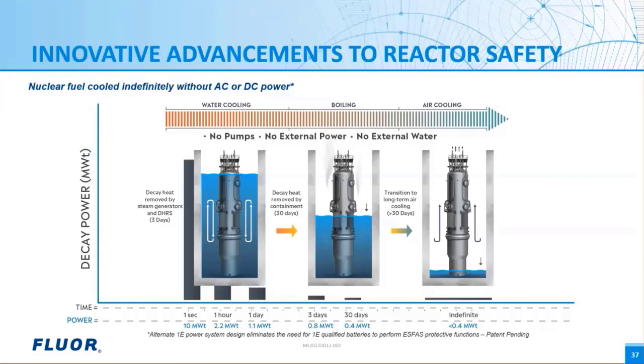Evacuating that volume also removes oxygen from the containment and thus it minimizes the possibility of a hydrogen deflagration. Finally, when the water level is below the level of the fuel, you're now cooling via air cooling. And that is sufficient air cooling to remove the decay heat, which is now down to a low level after 30 days. Note that while the reactor is known as walkaway safe, that's not the normal practice. Operator intervention and restorations of systems is the norm for cooling. So we would not normally use this progression. This is the emergency progression of decay heat removal.